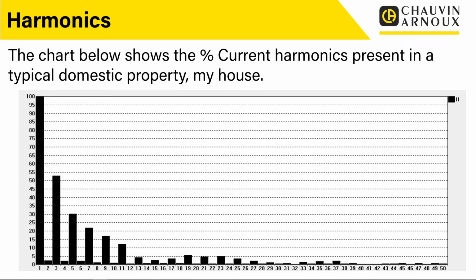So we've still got 30% of the current, a third basically, of the current that we had in the fundamental, in the fifth harmonic. And going on to the seventh harmonic, we're just over 20%. Ninth harmonic, we're at probably about 16, 17%. 11th harmonic, we're still over 10, so about 12%, something like that, and so on. And what's interesting, you can see with the 19th, 21st, and 23rd harmonics, the current actually starts to go back up again, so we've got some more harmonics going on, even up at those very, very high frequencies.